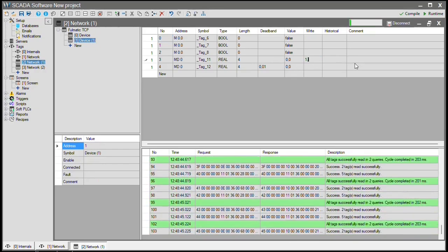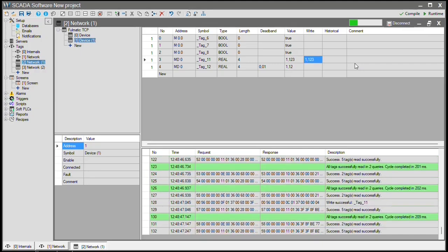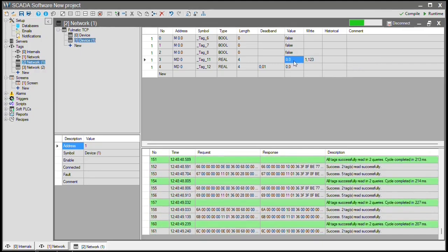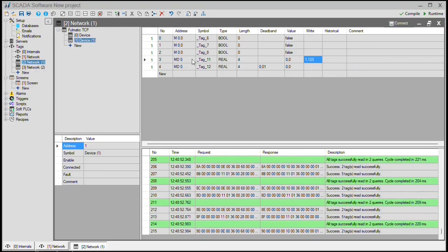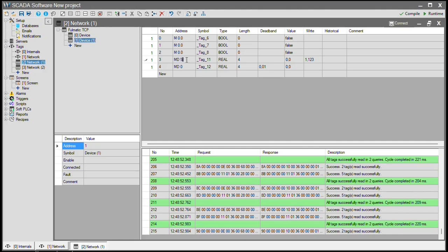When I enter a value like 1.123 from the right values column, I should not have used the address present in the PLC in the values section. Because the PLC program is constantly writing data to this address, I am making it a different address. Both should be the same address, both should be the same value. But deadband was applied to one of them.